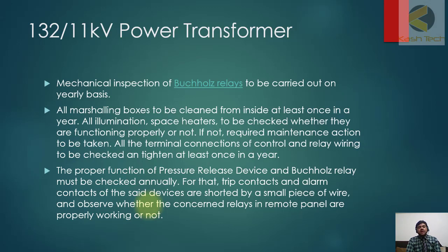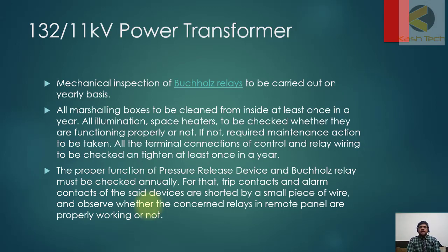All marshalling boxes should be cleaned from inside at least once a year. Illumination and space heaters should be checked to verify they are functioning properly; if not, the required maintenance action should be taken. All terminal connections of control and relay wiring should be checked and tightened at least once a year.